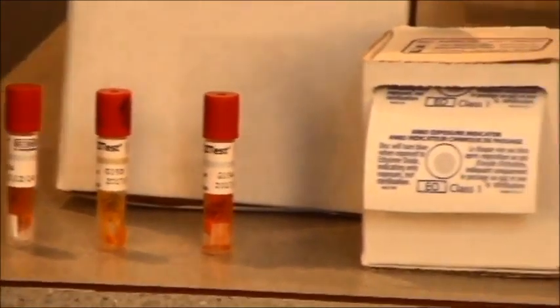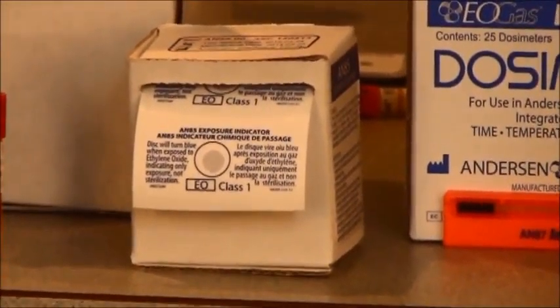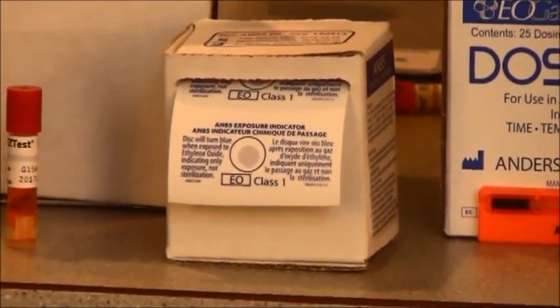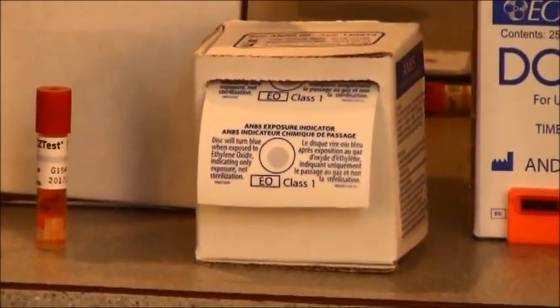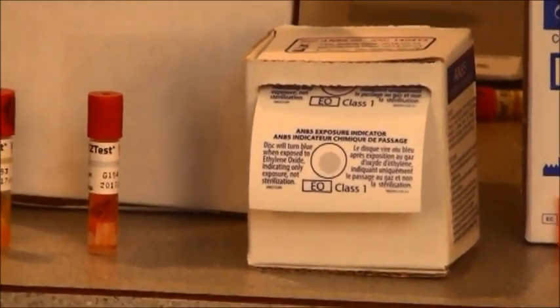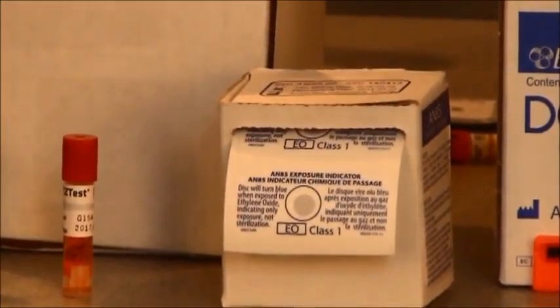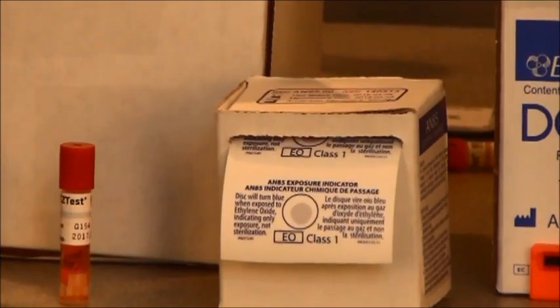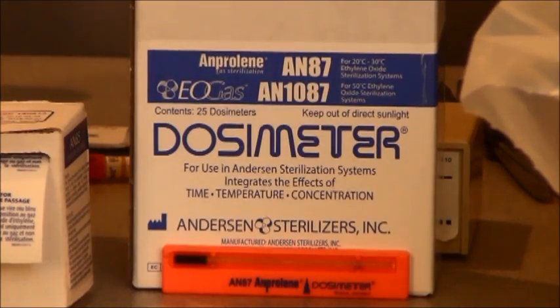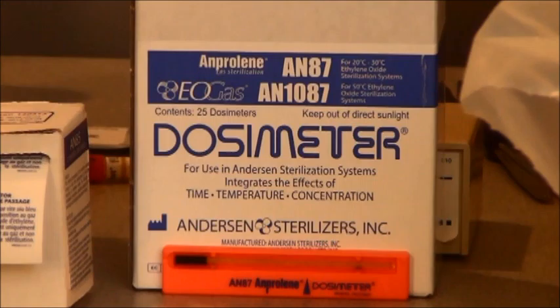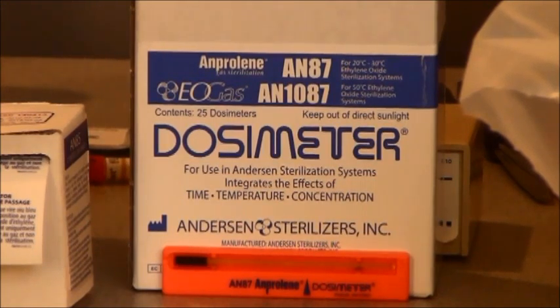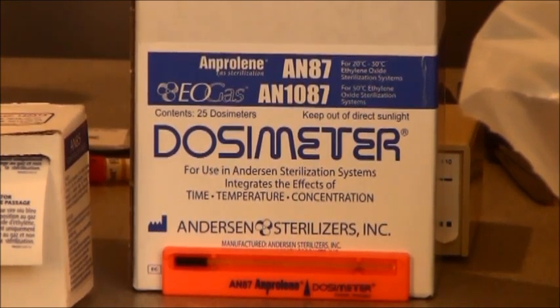In the center, you have your chemical exposure indicators, the AN85. These do not prove nor confirm sterilization. The color change only indicates that the items have been exposed to ethylene oxide. On the far right, you have your chemical exposure indicator, the AN87 dosimeter. The dosimeter provides immediate visual confirmation that the time and ethylene oxide concentration during the cycle were adequate for sterilization to occur.